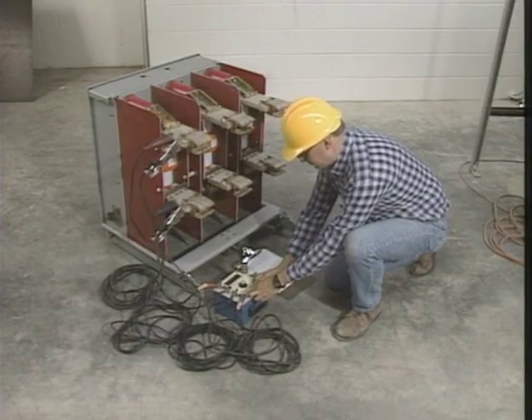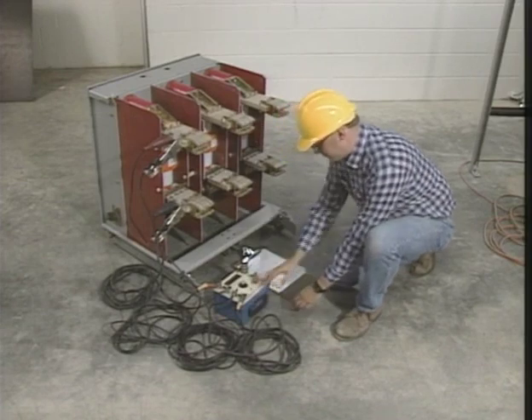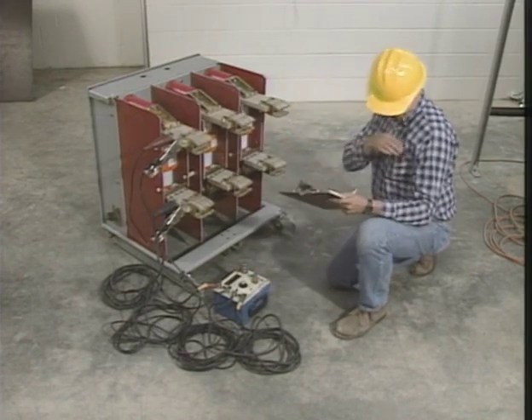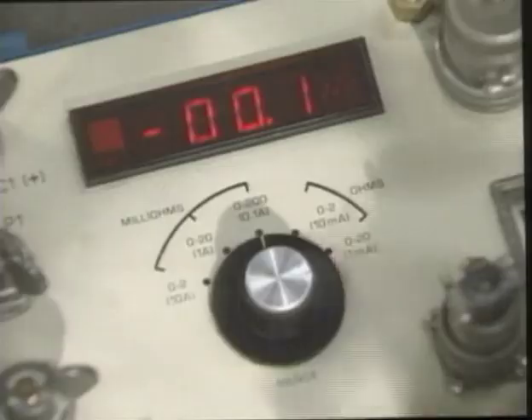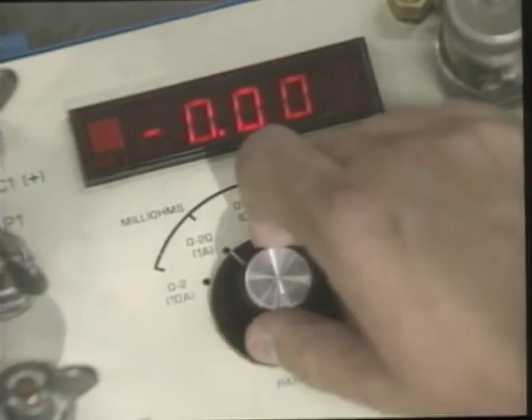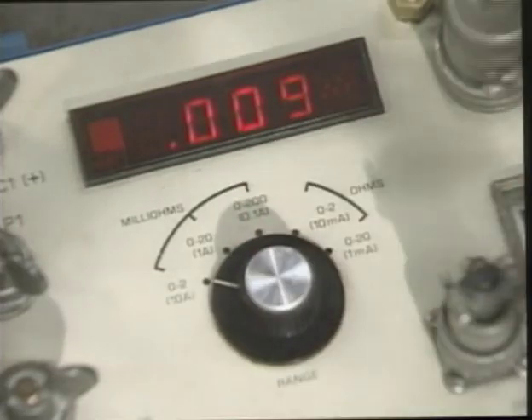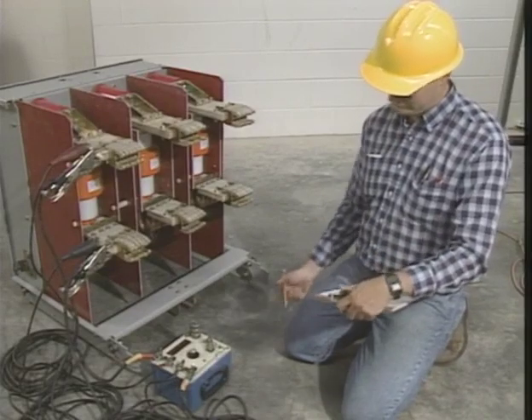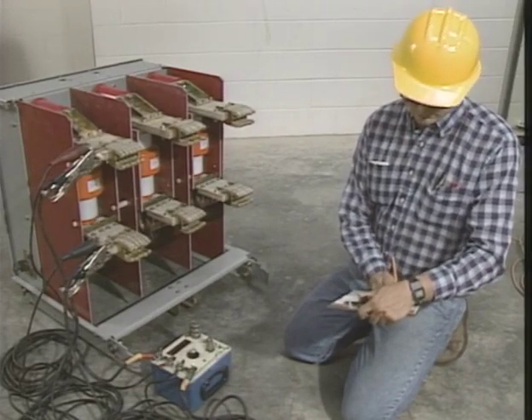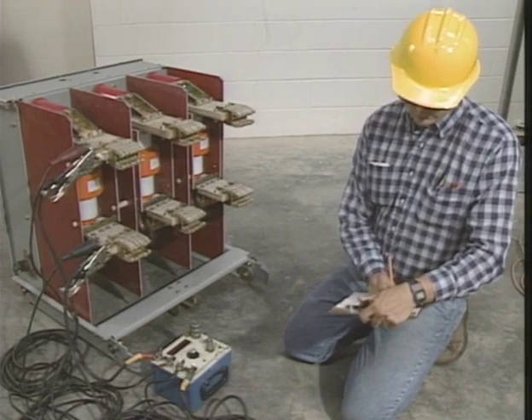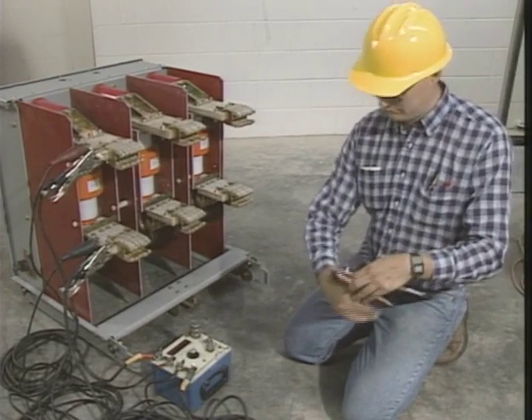In principle, the test is performed by passing a direct current through the closed contacts of the breaker and measuring the voltage drop across the contacts. The test instrument uses the current and voltage values to calculate and display the contact resistance. If the contact resistance exceeds an acceptable limit, the contacts may have to be cleaned or replaced.